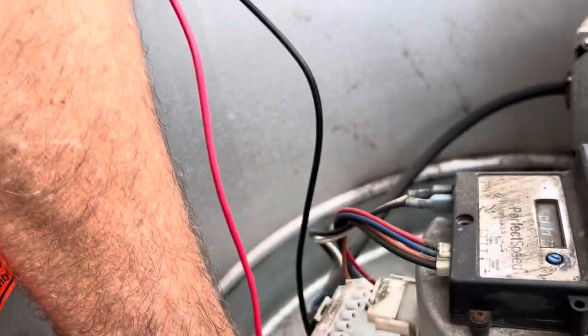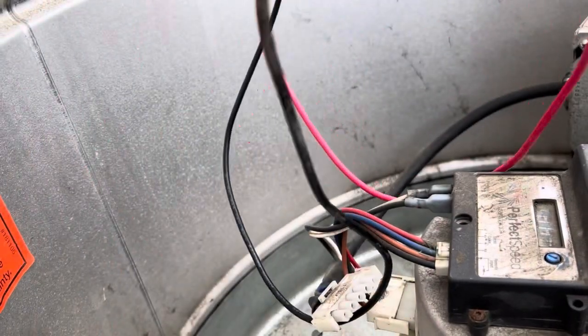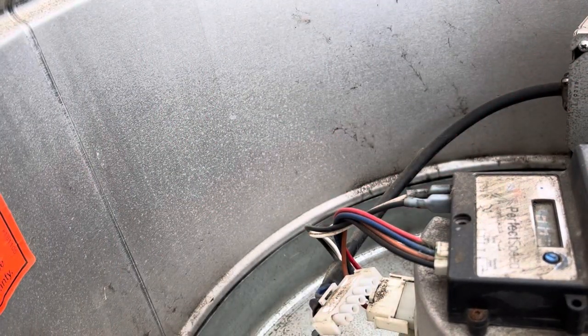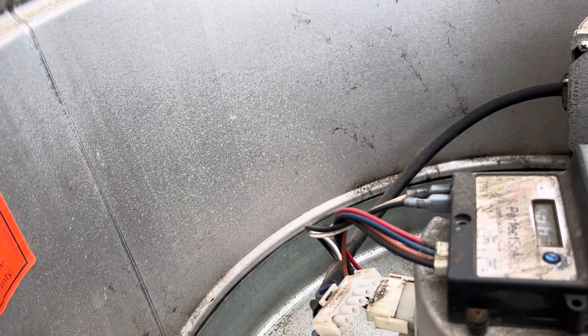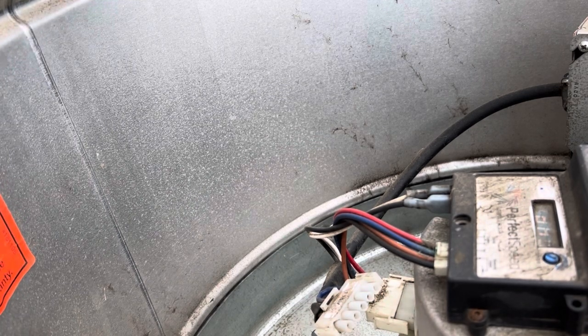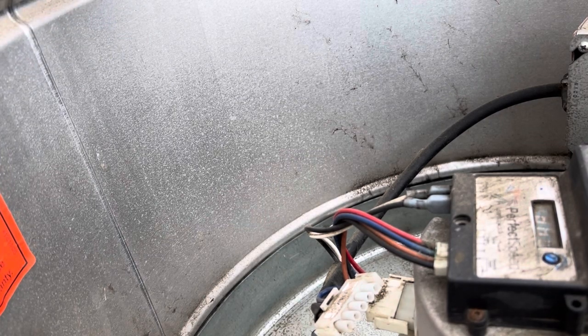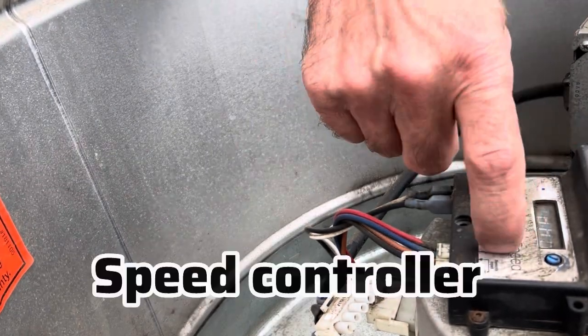If you know anything about ECM motors in the industry lately, when they work, they're great, but the longevity just isn't there yet. Usually it's the module on top that's bad, not the motor. But I just wanted to verify I actually do have power here. Like I said, I found the breakers for them and they weren't tripped, and now I'm going to go ahead and source this ECM motor.